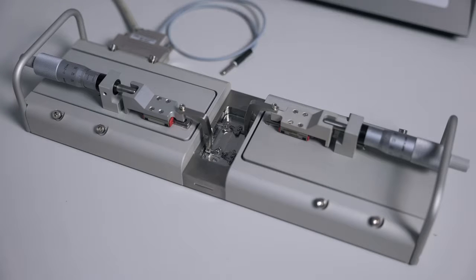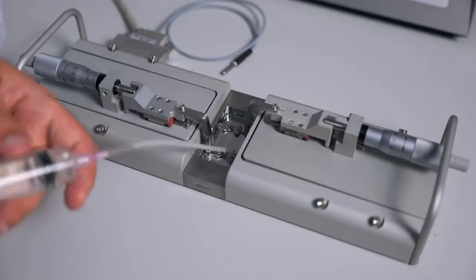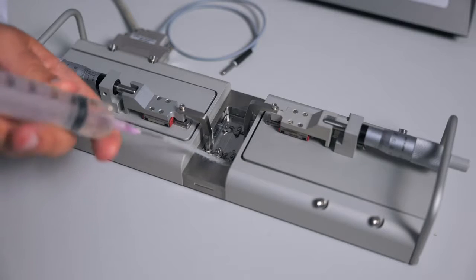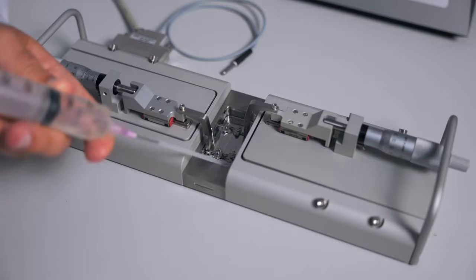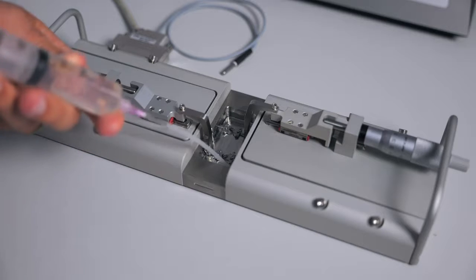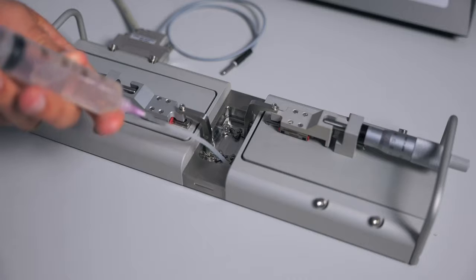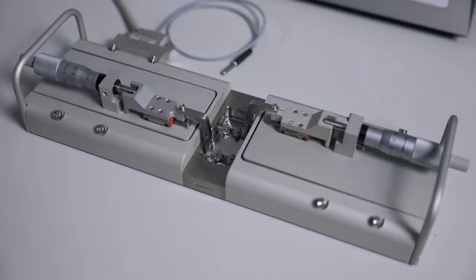The most severe cleaning that we would recommend is 3 molar nitric acid for a maximum of 2 minutes. No matter which of these procedures was used, you need to make sure to thoroughly wash the chamber several times with double distilled water. We don't recommend the heavy cleaning procedures too often, as these can damage the myograph chamber.